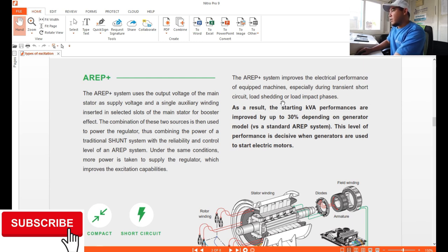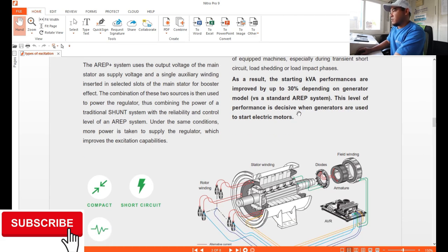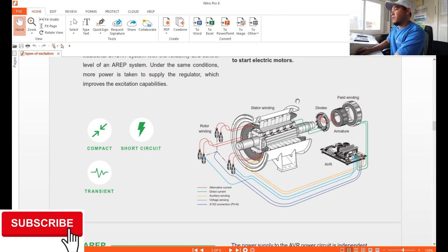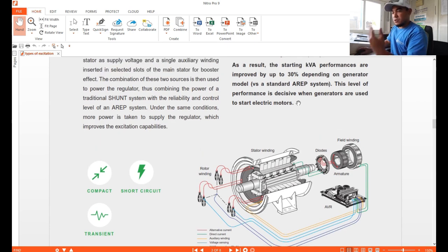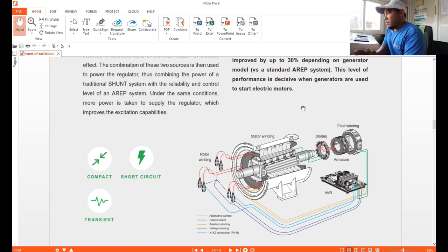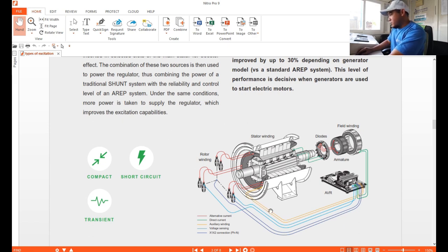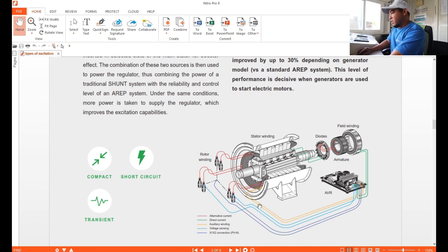The AREP+ system improves the electrical performance of equipped machines, especially during transient events — short circuit, load shedding, or load impact. This is a very good application when there is a short circuit for a short period of time or for impact loads. As you can see in the connections, there is an added yellow line representing the auxiliary winding inserted into selective slots — that is the one extra auxiliary winding.